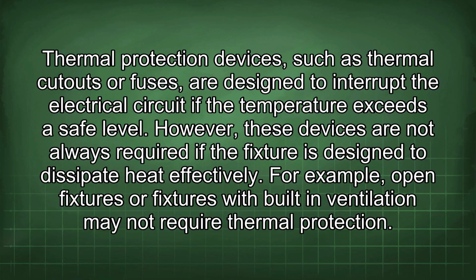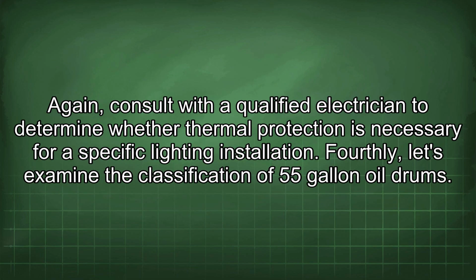Thermal protection devices, such as thermal cutouts or fuses, are designed to interrupt the electrical circuit if the temperature exceeds a safe level. However, these devices are not always required if the fixture is designed to dissipate heat effectively. For example, open fixtures or fixtures with built-in ventilation may not require thermal protection. Again, consult with a qualified electrician to determine whether thermal protection is necessary for a specific lighting installation.